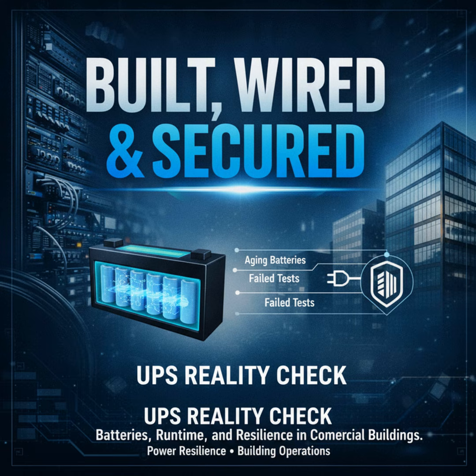If I can add one final operational note, include realistic failure scenarios in tabletop exercises. Walk through a 3-minute outage, a sustained 15-minute outage, and a battery failure in warm weather scenario. Ask what breaks for each and document the mitigation. Those simple exercises align teams faster than a 100-page manual ever will.